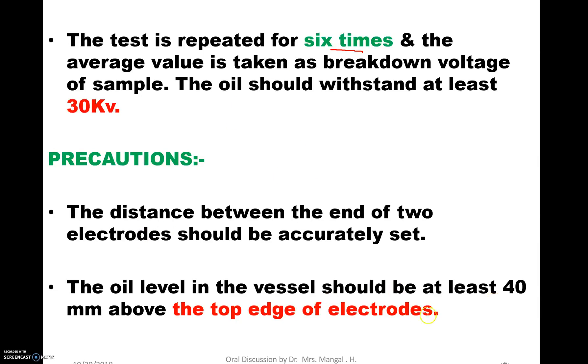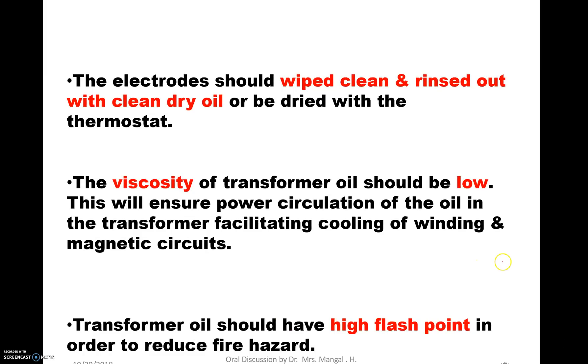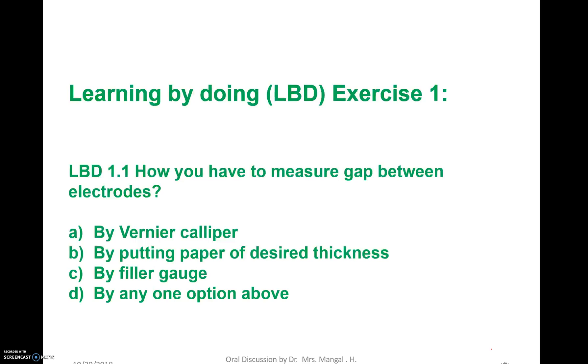The distance between the two electrodes must be accurately set — if it is different, breakdown voltage will be different. Oil level should be as per IS specifications as that also affects breakdown voltage. Electrodes and test cells should be thoroughly cleaned and rinsed with dry oil, because moisture or impurities will change the breakdown voltage. Viscosity of transformer oil should be low, as viscosity also affects breakdown voltage. Transformer oil should also have a higher flash point — if the flash point is low, it may cause fire in the oil.